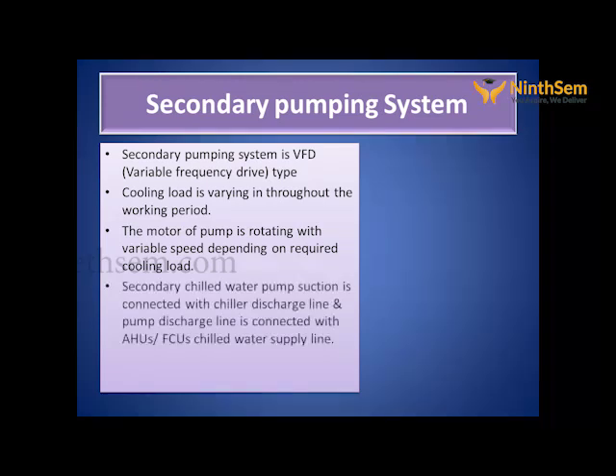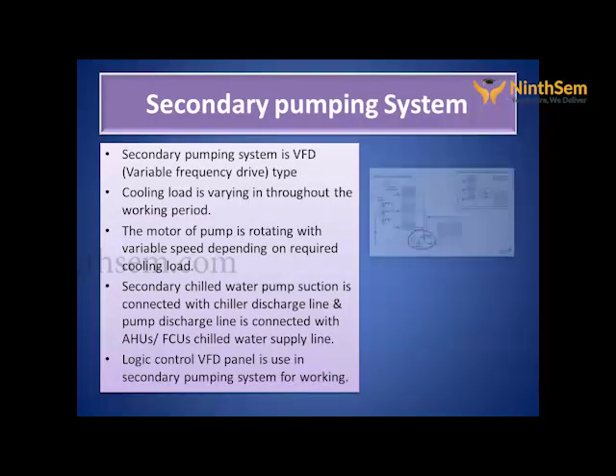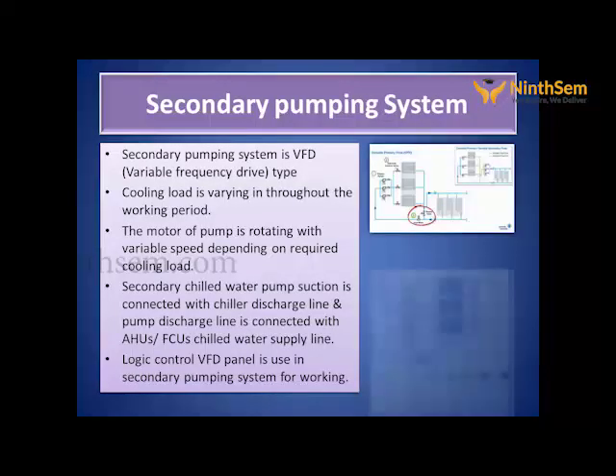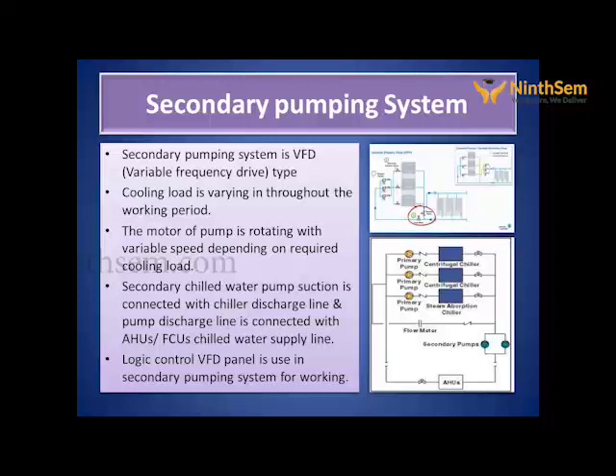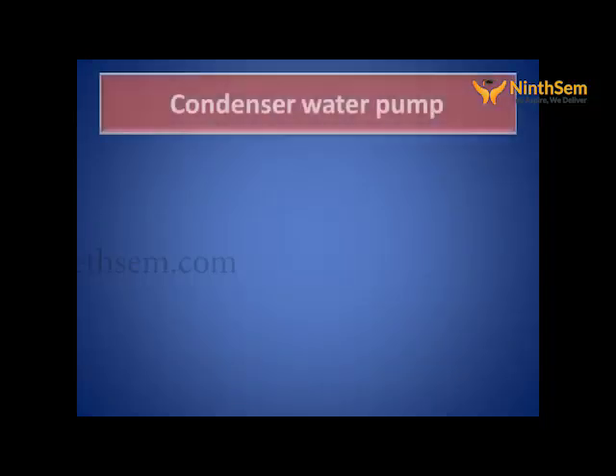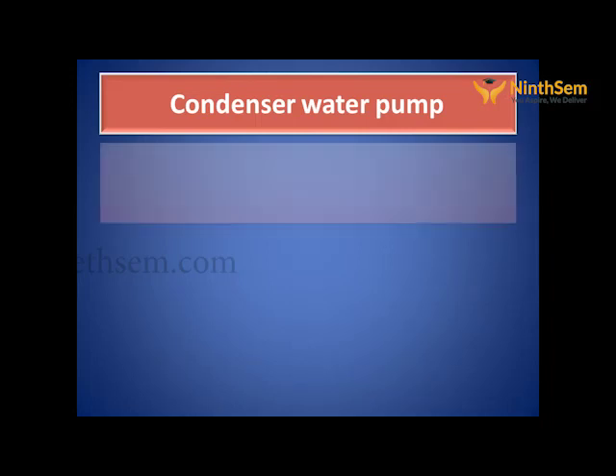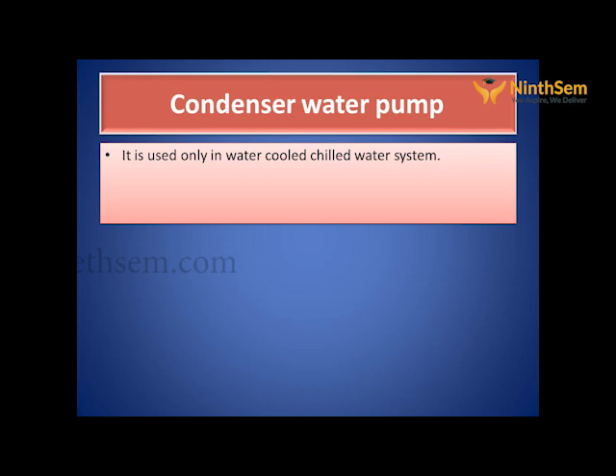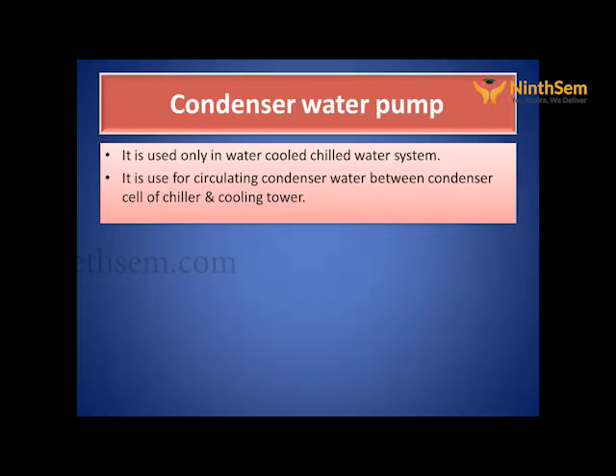The secondary chill water pump suction is connected with chiller discharge line, and pump discharge line is connected with AHUs and FCUs chill water supply line. Logic control panel VFD is used in secondary pumping system for working. Now, condenser water pump. Condenser water pumps are used only in water-cooled chiller water system. Condenser water pump is used for circulating condenser water between condenser shell of chiller and cooling tower.